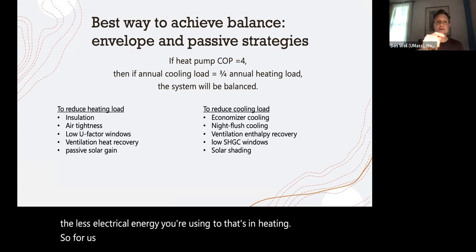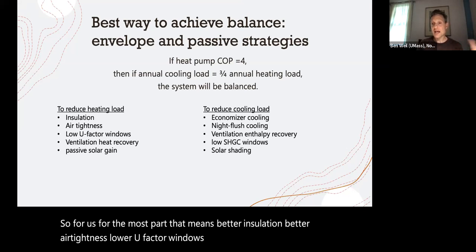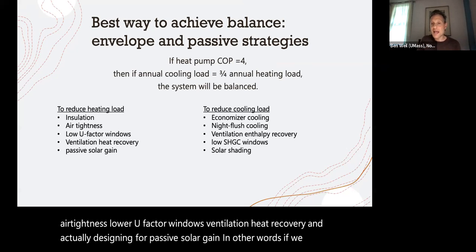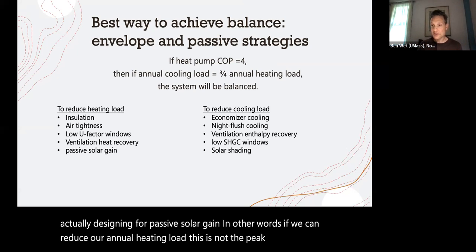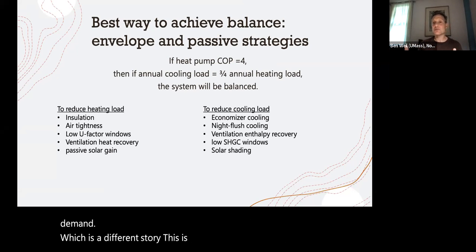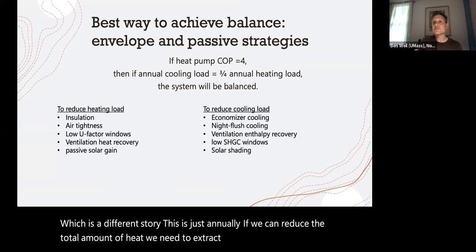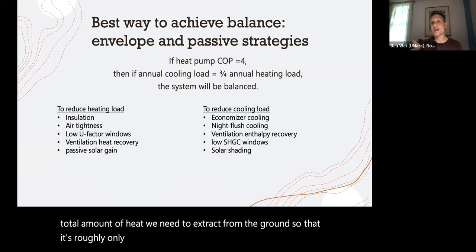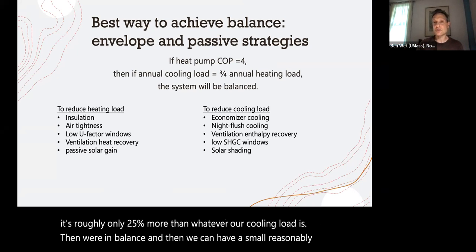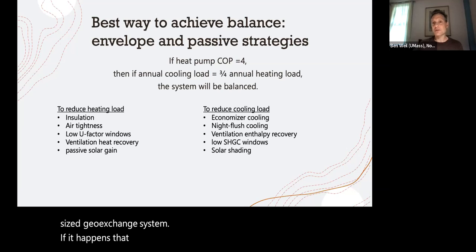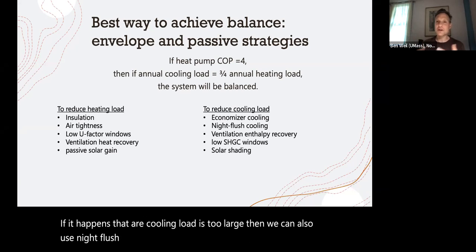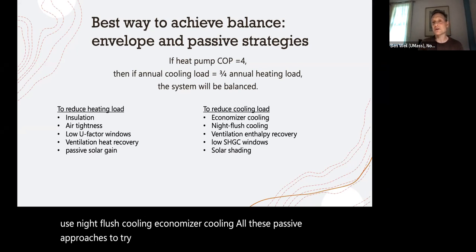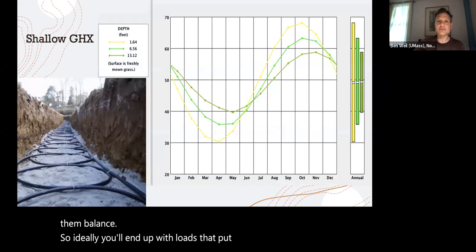So for us, for the most part, that means better insulation, better air tightness, lower U-factor windows, ventilation heat recovery, and designing for passive solar gain. In other words, if we can reduce our annual heating load, this is not the peak heating demand, which is a different story, this is just annually, if we can reduce the total amount of heat we need to extract from the ground so that it's roughly only 25% more than whatever our cooling load is, then we're in balance. And then we can have a small, reasonably sized geoexchange system. If it happens that our cooling load is too large, then we can also use night flush cooling, economizer cooling, all these passive approaches to reduce the cooling load, to try to make them balance. So ideally, you end up with loads that put the geoexchange system in balance.